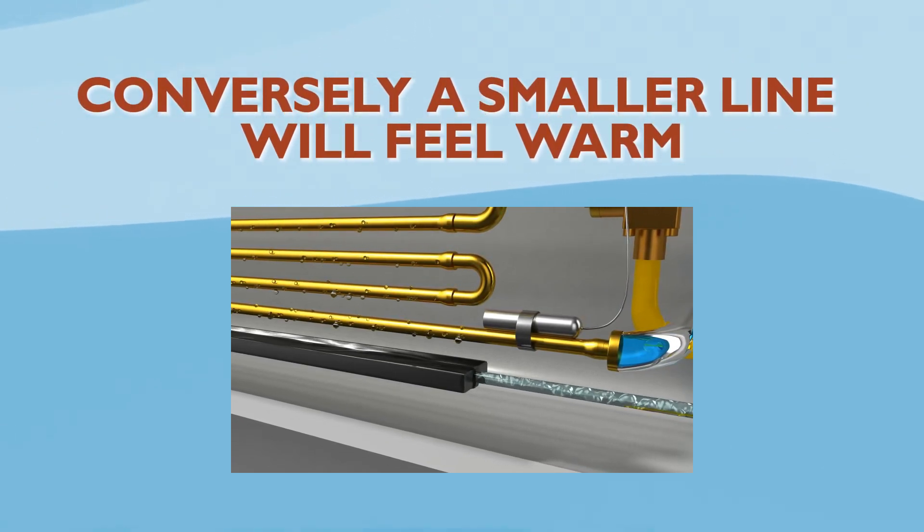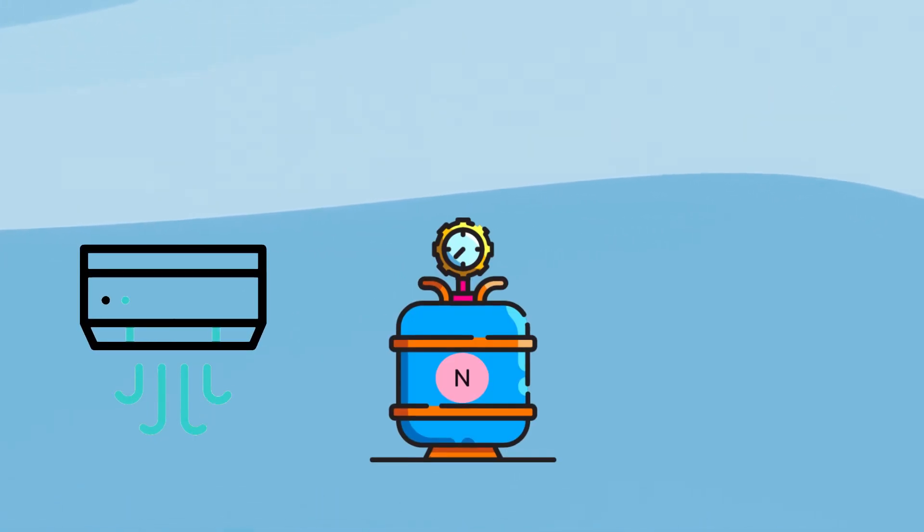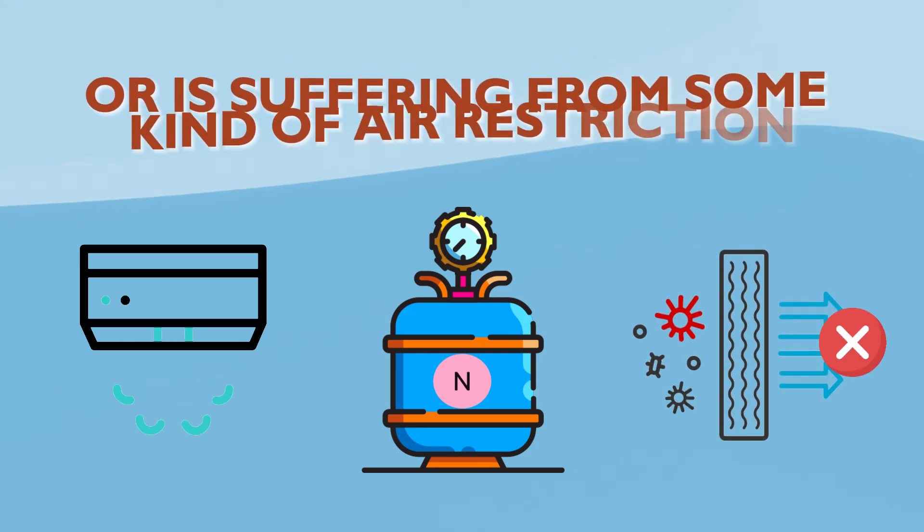Conversely, a smaller line will feel warm while the air conditioner is running. However, if you see ice on the lines, you likely have a system that is low on refrigerant or is suffering from some kind of air restriction.